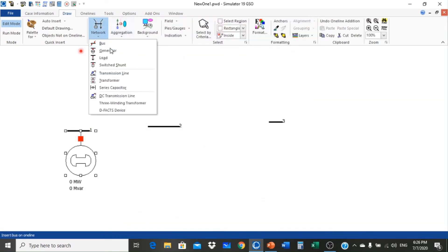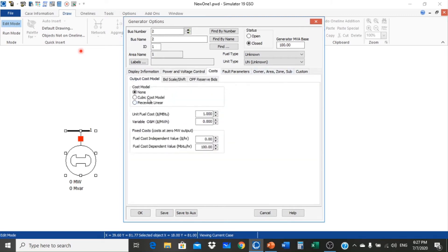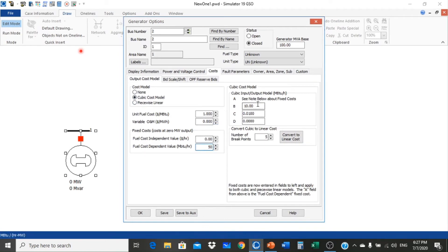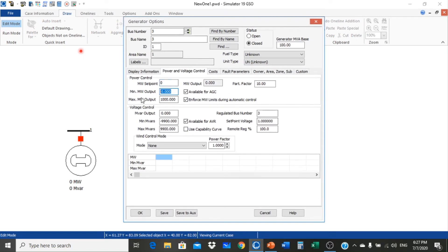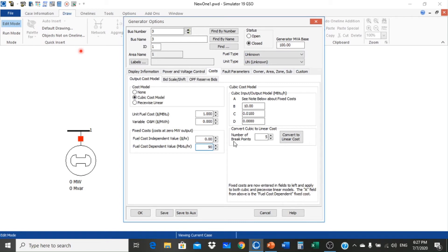Similarly, we set up generator 2 at bus 2 with minimum 50 MW and maximum 125 MW, using the cubic cost model. Its coefficients are: A = 50, B = 2.7, C = 0.01. Then we connect generator 3 at bus 3 with minimum 50 MW and maximum 100 MW. Its coefficients are: A = 90, B = 1.6, C = 0.007.